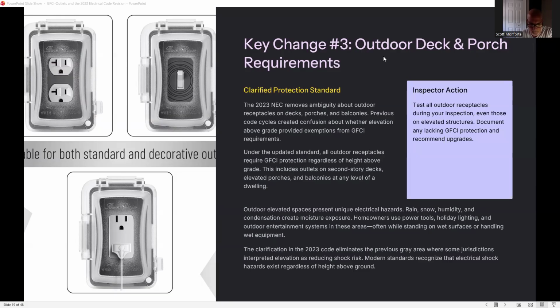Outdoor elevated spaces present unique electrical hazards. Rain, snow, humidity, and condensation create moisture exposure. Homeowners use power tools, holiday lighting, and outdoor entertainment systems in these areas, often while standing on wet surfaces or handling wet equipment. The clarification in the 2023 code eliminates the previous gray area where some jurisdictions interpreted elevation as a reduced shock risk.